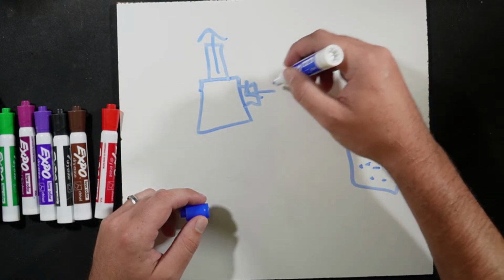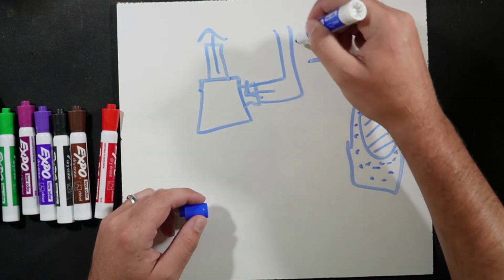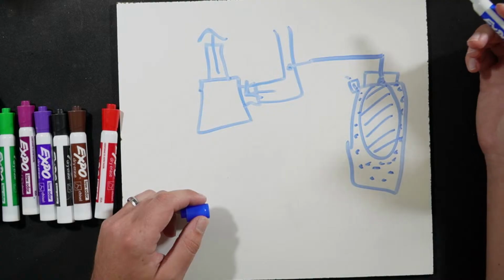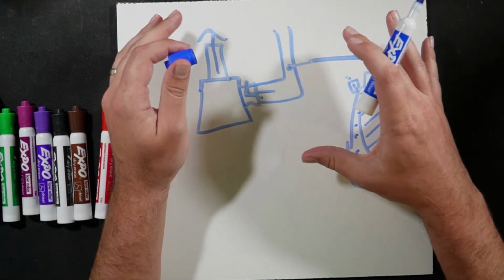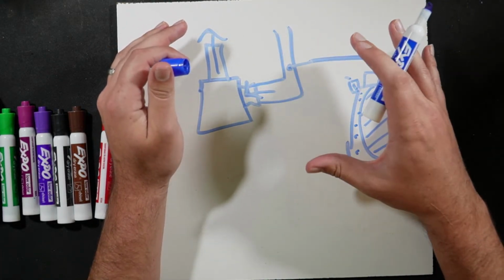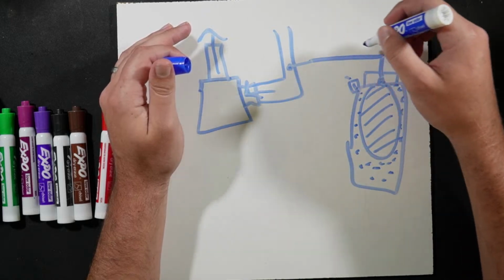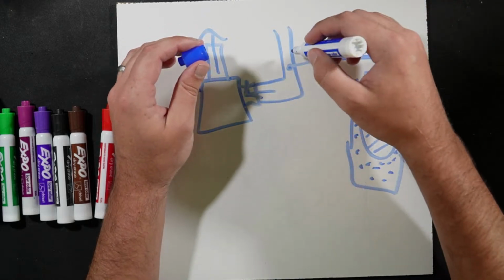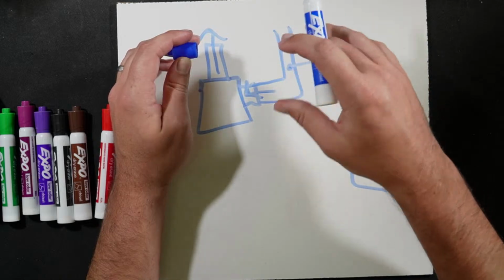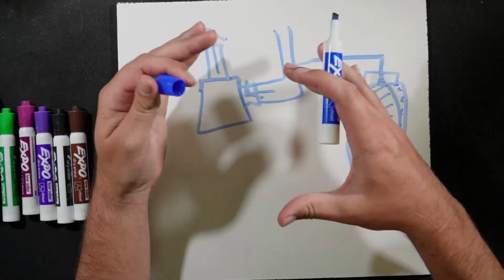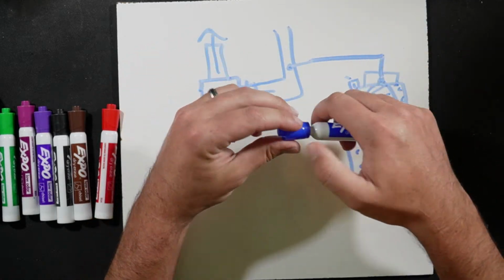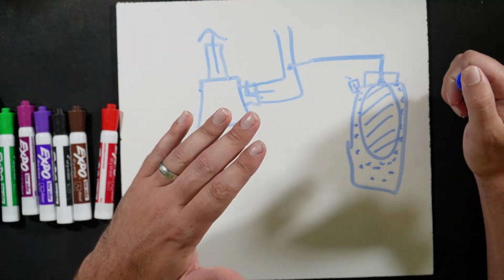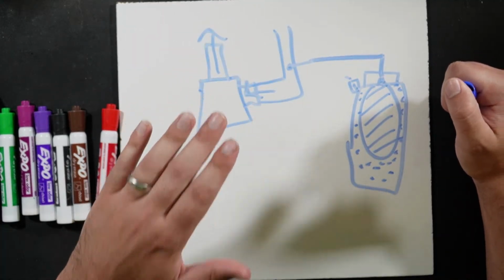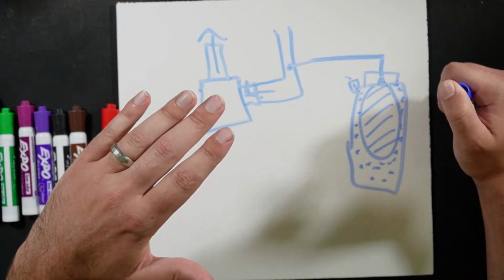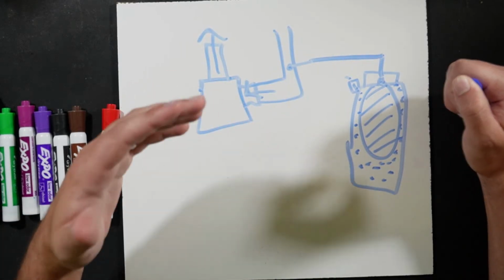So we would end up connecting to this pipe here on the pump. This is the same place you would also have your makeup water and such connected as well. What's going to happen is the loop pressures will naturally fluctuate, which they will. As water changes temperature in the loop, the pressure will increase or decrease with that change in temperature.